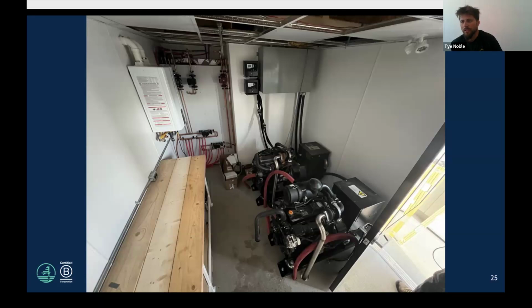We're always going in hotter than that, and then we have mixing valves. But this propane hot water tank is only a backup — it's just redundant heat. It's rarely turned on, because the cold water coming into it is actually hotter than it can make it. So it's just another redundant piece in case there was ever engine failure, or during the day when there's a lot of dishes being done and you're running on battery — we don't have to start the engine just for heat.